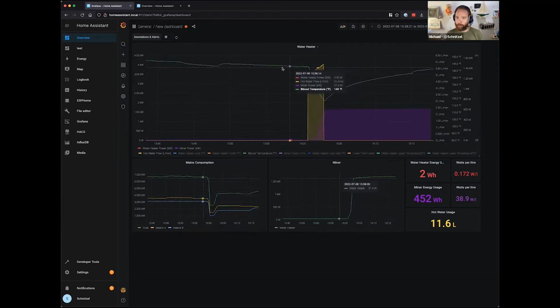That's the temperature of the Mixer before, during, and after. Before, the Mixer was at 143 Fahrenheit, that was just the temperature from last time. Then as soon as the cold water comes in, because it goes through the plate exchanger, the temperature of the Mixer drops massively, down to 119 Fahrenheit, and then slowly creeps back up. It's already at 141 degrees again.